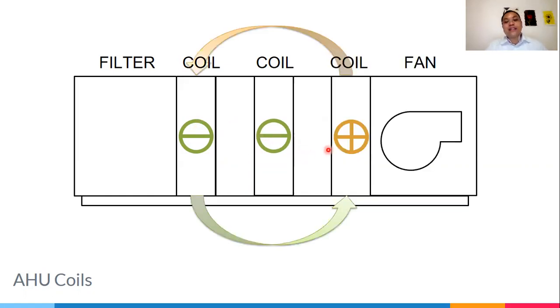Sometimes there's even a three-step setup: pre-cool, cooling coil, then heating again. Same as before, the heating coil generates artificial heat so you can reach your room conditions. There's also what I have an arrow on here - this is part of the run-around coil. The heat that enters here gets cooled, and this cooled energy is given back to the air and gets heated up, so you're able to reach your desired room condition.